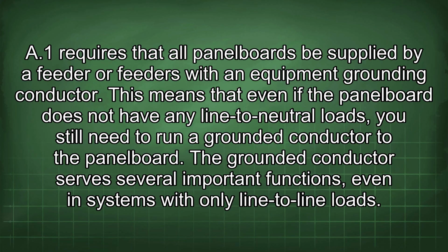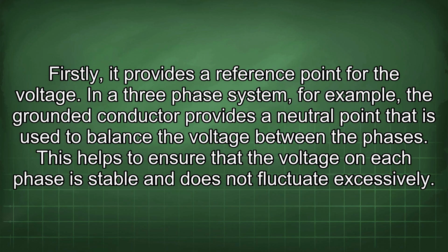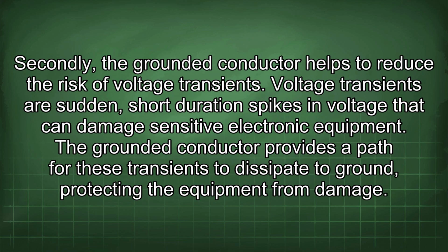The grounded conductor serves several important functions, even in systems with only line-to-line loads. Firstly, it provides a reference point for the voltage. In a three-phase system, for example, the grounded conductor provides a neutral point that is used to balance the voltage between the phases. This helps to ensure that the voltage on each phase is stable and does not fluctuate excessively. Secondly, the grounded conductor helps to reduce the risk of voltage transients. Voltage transients are sudden, short-duration spikes in voltage that can damage sensitive electronic equipment. The grounded conductor provides a path for these transients to dissipate to ground, protecting the equipment from damage.